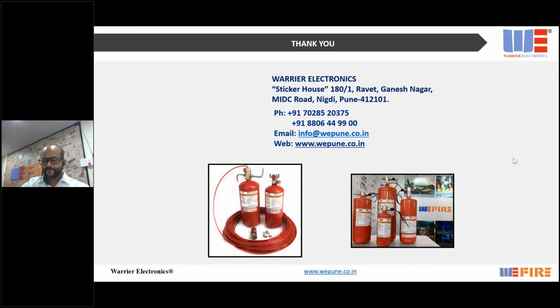We can lay out pipelines only to wherever the area to be covered is. Absolutely, like that. If the pipelines are not longer, there is a limitation again; discharge pipes cannot be beyond 4 meters. So ideally these are small systems which can be placed just beside where a fire hazard is present. For example, in a CNC machine, we mount it above the cylinder itself, so there is no additional space required. These are so small.